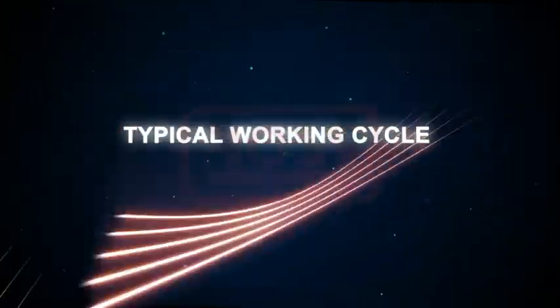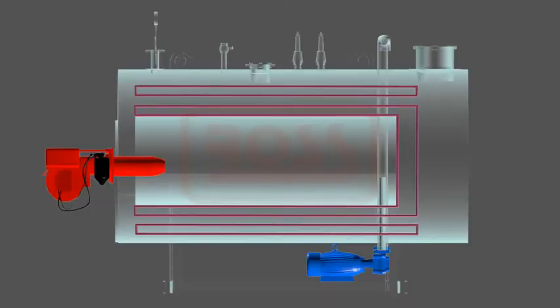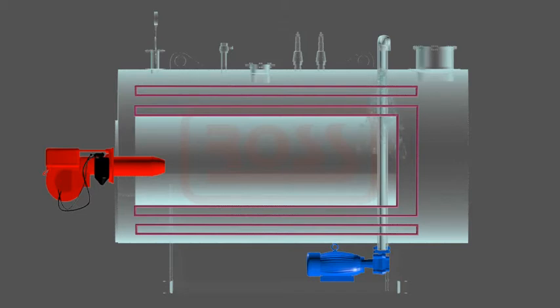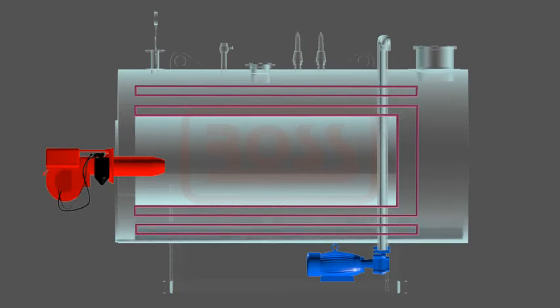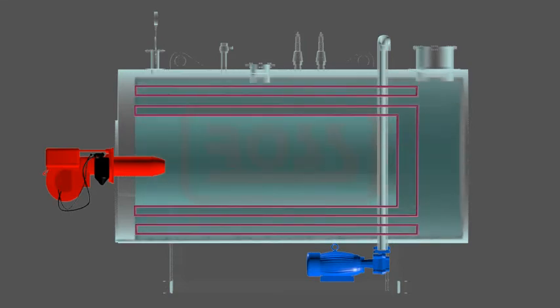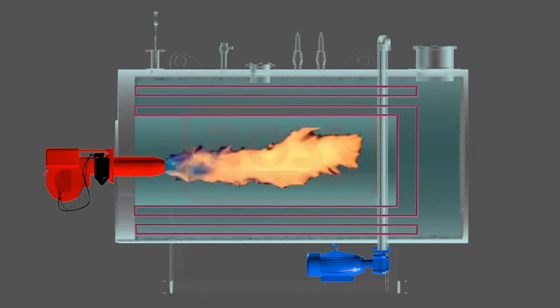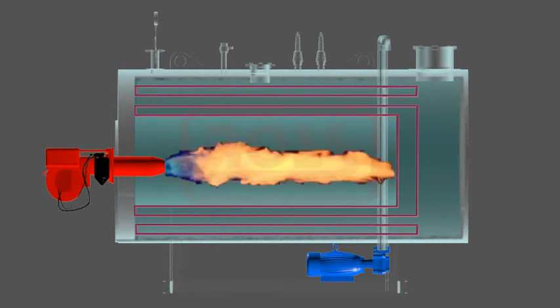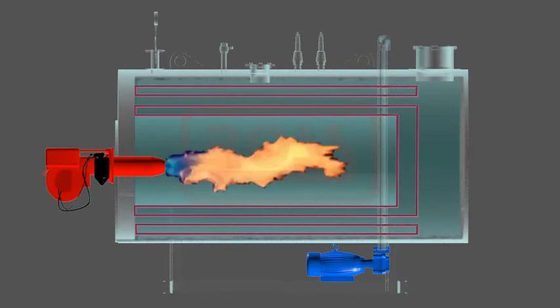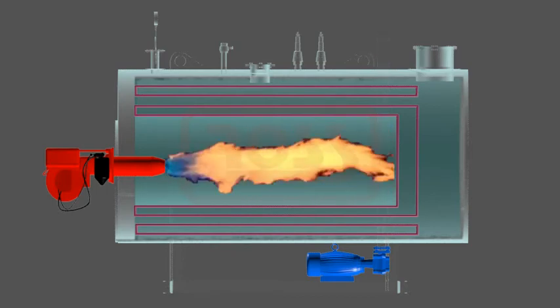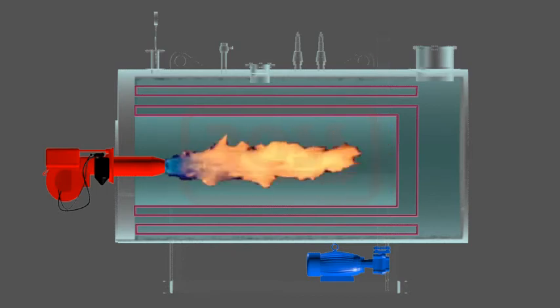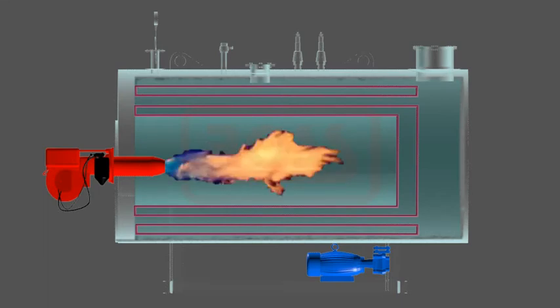Typical working cycle: Treated soft water is filled in the hot water generator. Hot water pump is run continuously to circulate the hot water through the hot water generator and process. Fuel firing switch is put on to run the burner through its automatic stages of pre-purge, ignition and fuel firing modes.